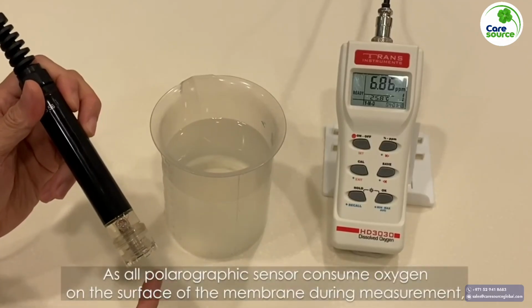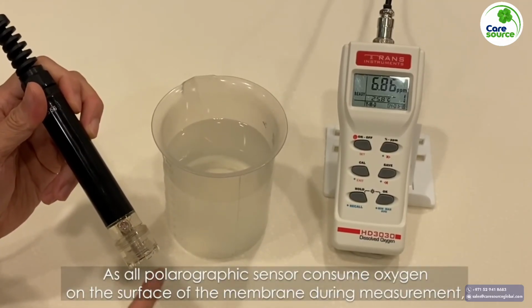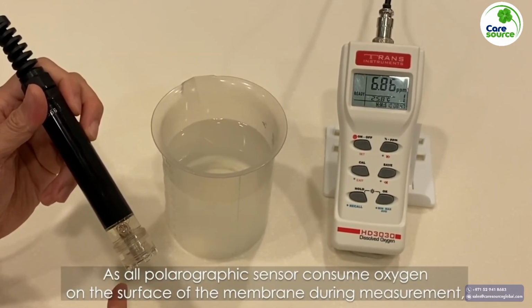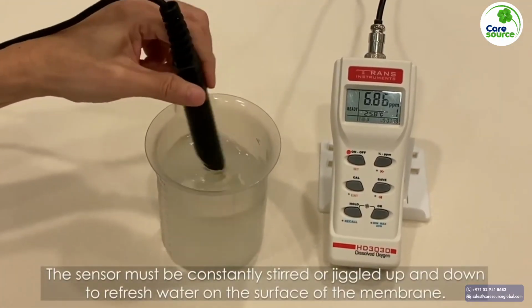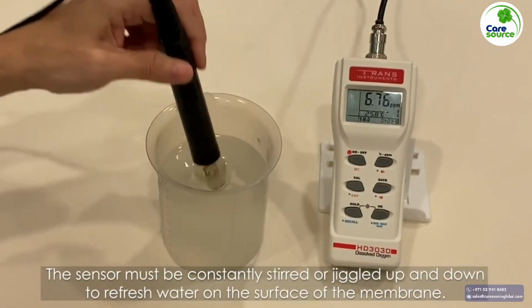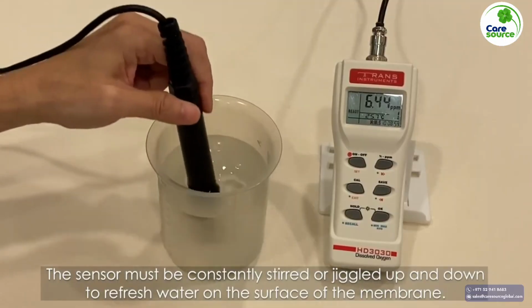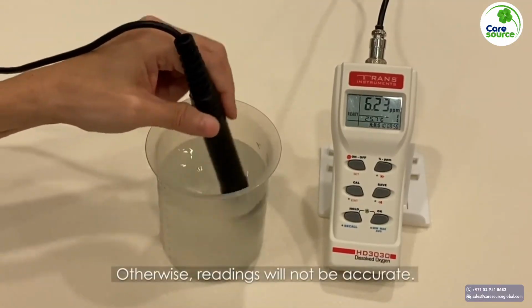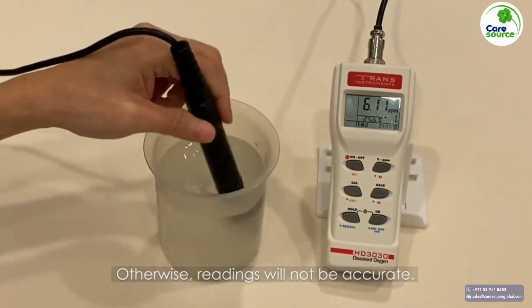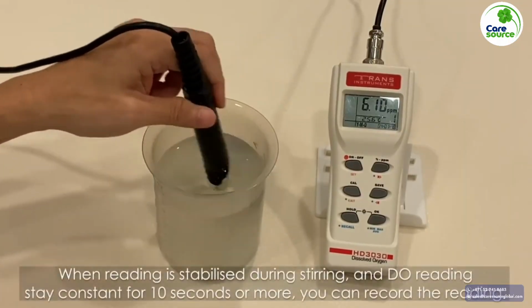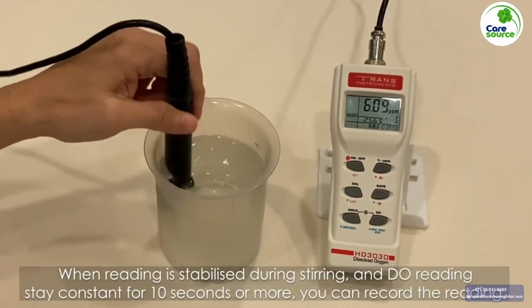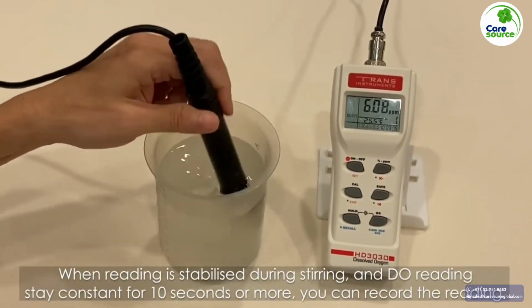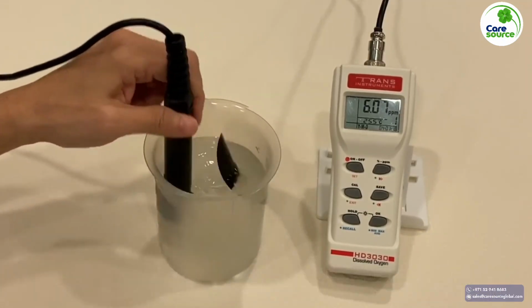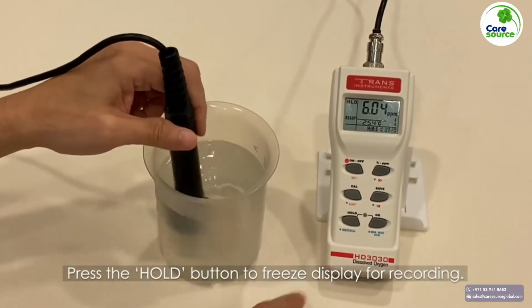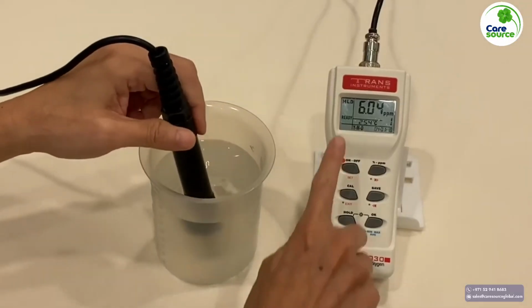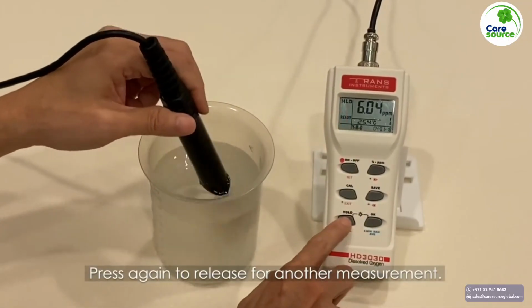As all polarographic sensors consume oxygen on the surface of the membrane, during measurement the sensor must be constantly stirred or jiggled up and down to refresh water on the surface of the membrane. Otherwise, the reading will not be accurate. When the reading is stabilized during stirring and the DO reading stays constant for 10 seconds or more, you can record the reading. Press the Hold button to freeze the display for recording. Press again to release for another measurement.